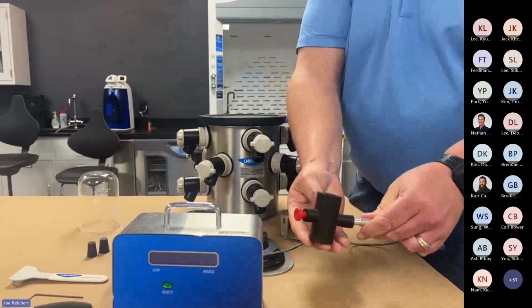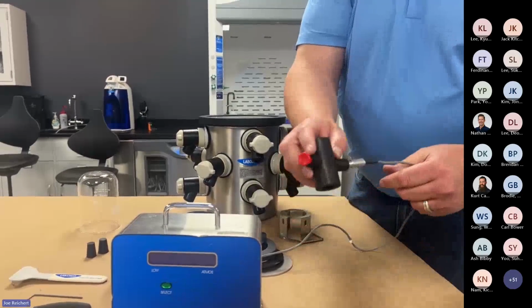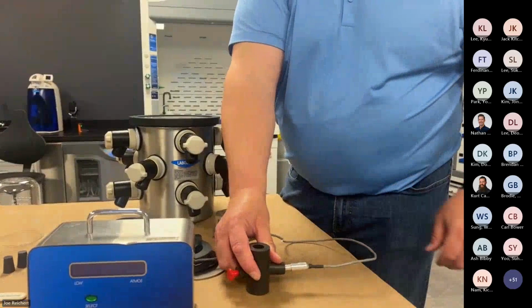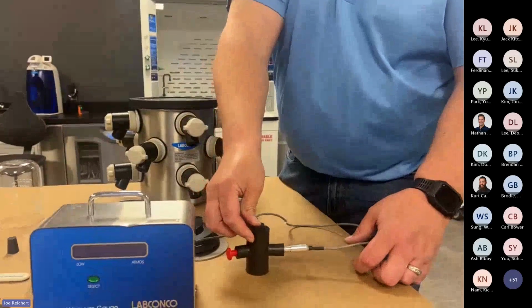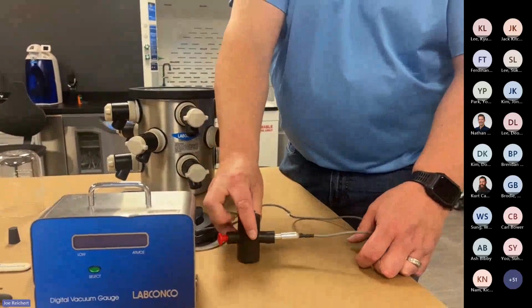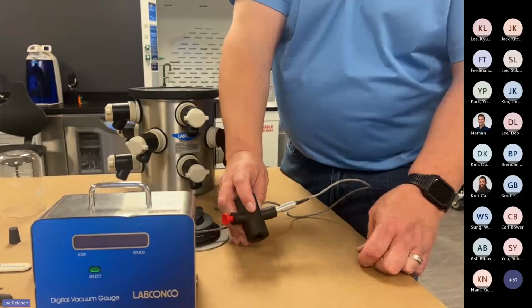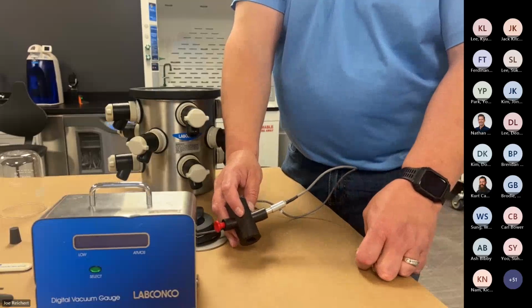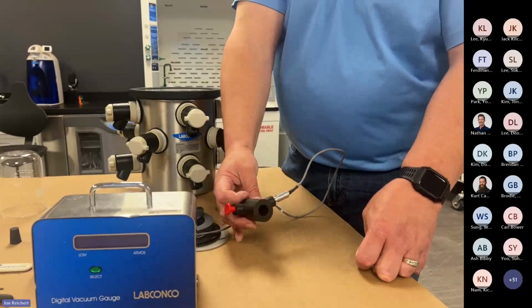sensor on it that we can insert into something like this port on the side. You just insert it, stick this on top of your vacuum pump, and then you could use a rubber stopper to plug the top of this. And now you have a perfectly sealed coupling that you can measure your vacuum pump directly and accurately to know, where is my issue.